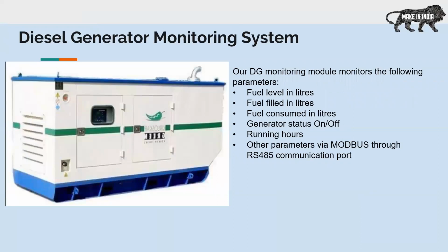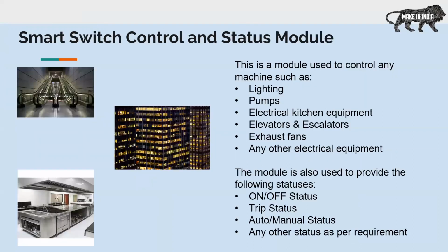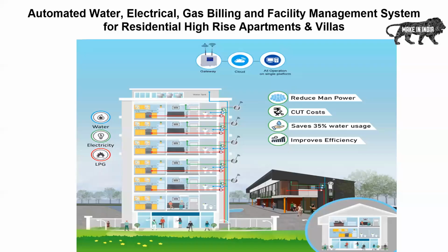Then we have a diesel generator monitoring system where we provide fuel level monitoring, that is fuel level, fuel filled, fuel consumed, generator on/off status, and if it has an RS485 communication port, we can provide additional parameters. Then we have the switch control and status module, which can be used to control any machine such as lighting, pumps, electrical kitchen equipment, elevators, escalators, exhaust fans, etc. The status module can provide on-off status, trip status, auto/manual status, and any other status as per requirement.